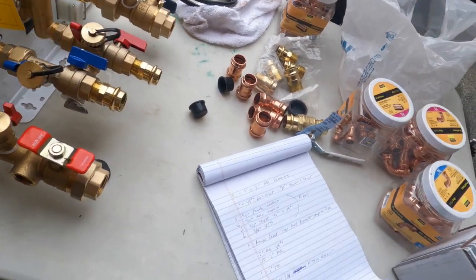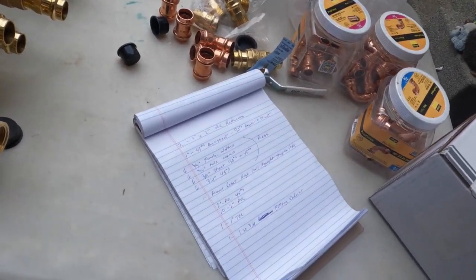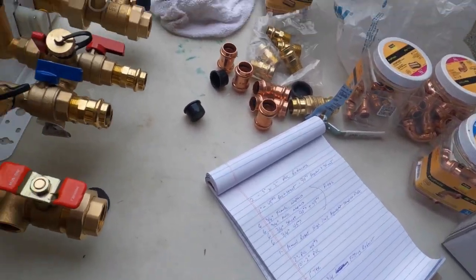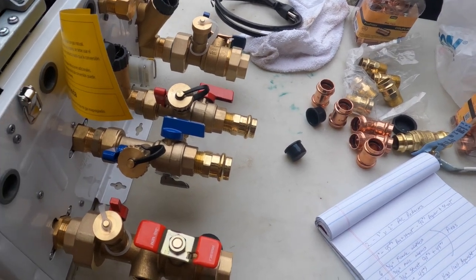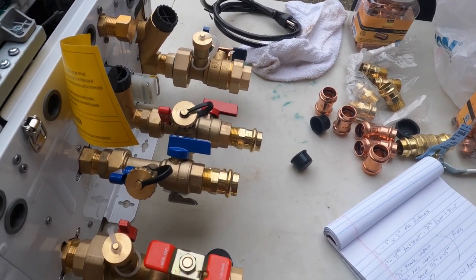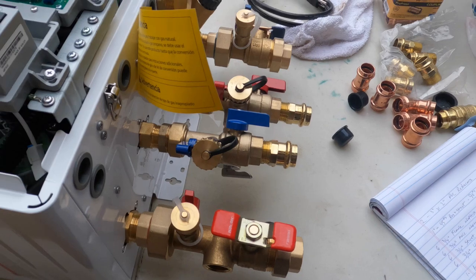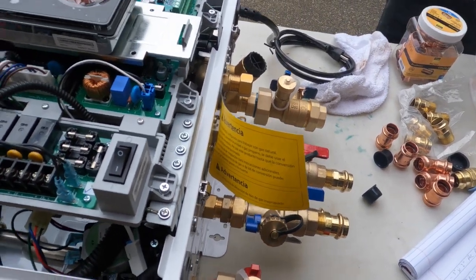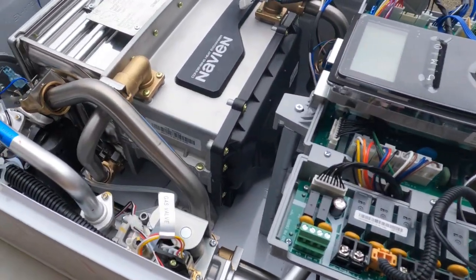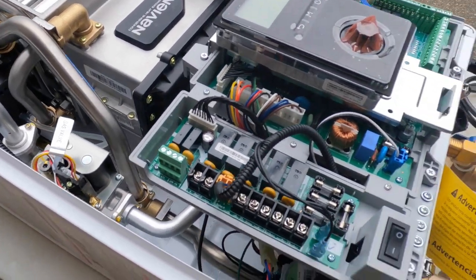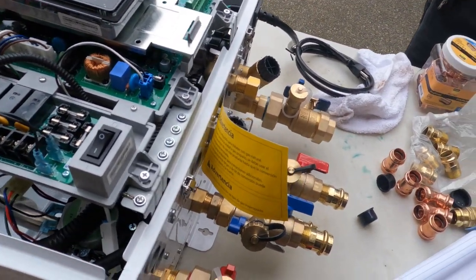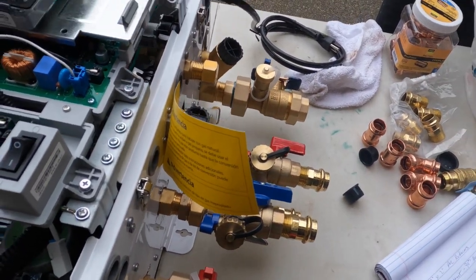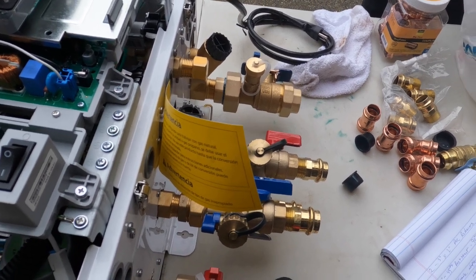That's it so far. I'm just trying to determine all the fittings and things we need to go get. We're also going to be putting in a mixing valve on the domestic hot water side, so that we can avoid any pockets of extremely hot water entering the domestic side of the system. A lot of folks don't do that, but it is a very nice thing to do.